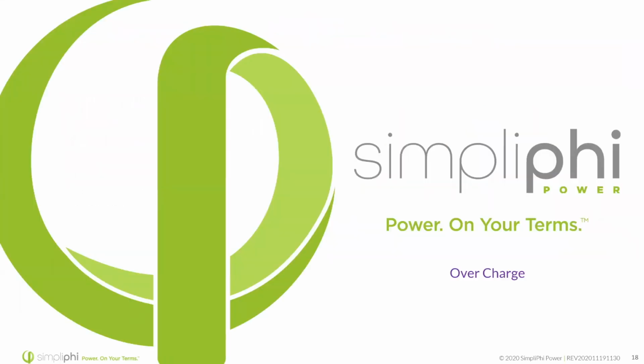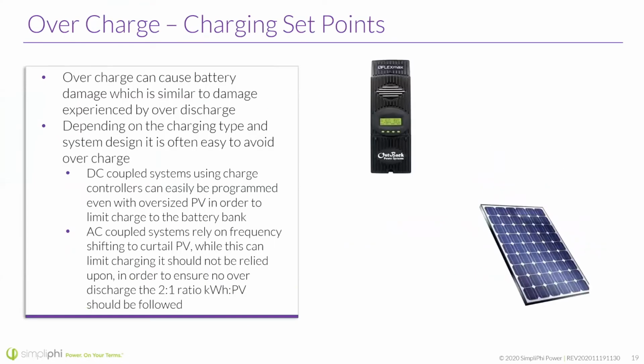Okay, moving on, overcharge. Overcharge is super similar as far as the damage seen from over discharge, but let's just look through some of this here. Overcharge can cause battery damage, which is similar to the damage experienced by over discharge. Depending on the charging type and system design, it's super easy to avoid overcharge. I would say it's 1,000 times easier to avoid overcharge than it is to avoid over discharge, because the sizing does kind of mess people up sometimes if they're just thinking about customer needs and not the inverter to the battery size. The charging is really easy.